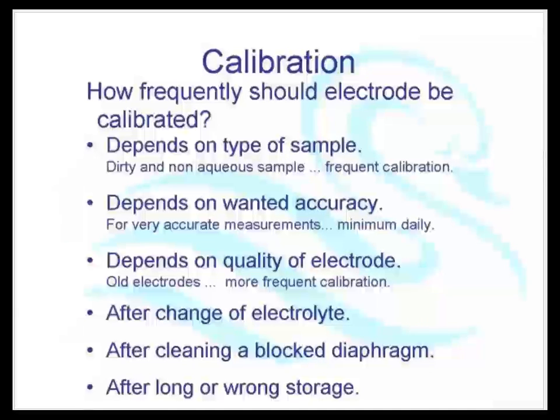So a pH probe is just a constant battle to keep the thing in service. You can't even keep a spare in the cupboard, because the whole time it's sitting on the shelf in the cupboard, it's losing its ability, it's going off. So if you buy 2 pH probes, you mount one of them and you stick the other one in the cupboard, by the time the first one's stuffed, so's the second one. You actually have to order the spare to arrive on site when you need the next one. They're completely rubbish. And like I say, the only reason we use them is because of legislation.